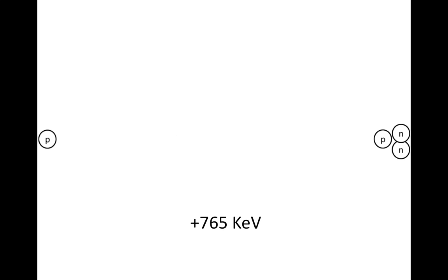When a neutron comes into contact with helium-3, it splits into a proton and a triton, with 765 kiloelectron volts of kinetic energy in the proton and triton. The detector's shell is made of metal, in our case aluminum. When the detector has a high voltage going through it, the energy produced by the reaction can be recorded.